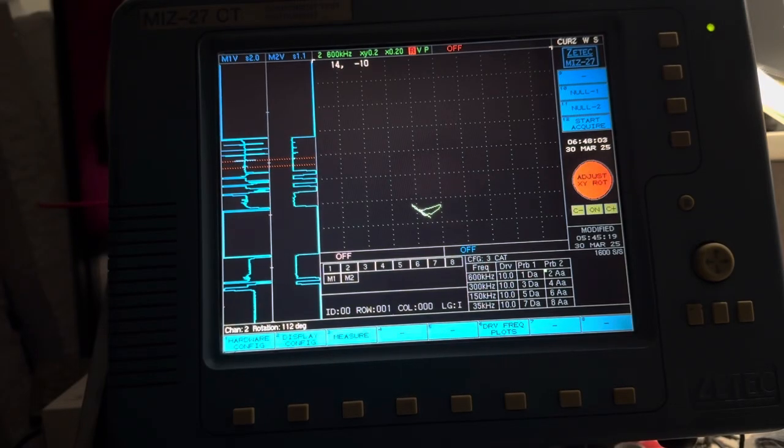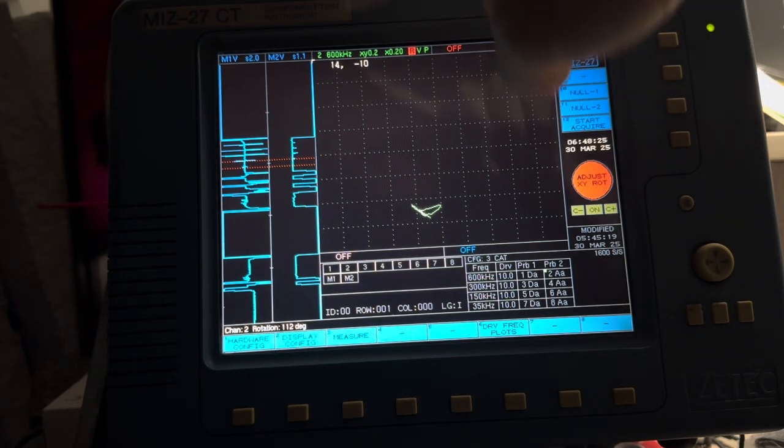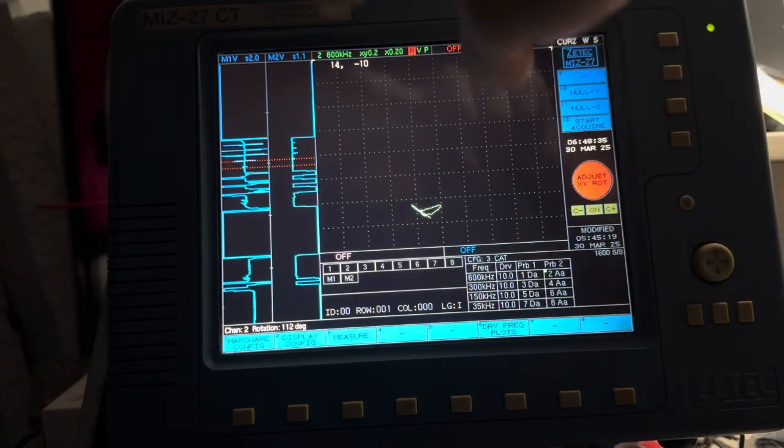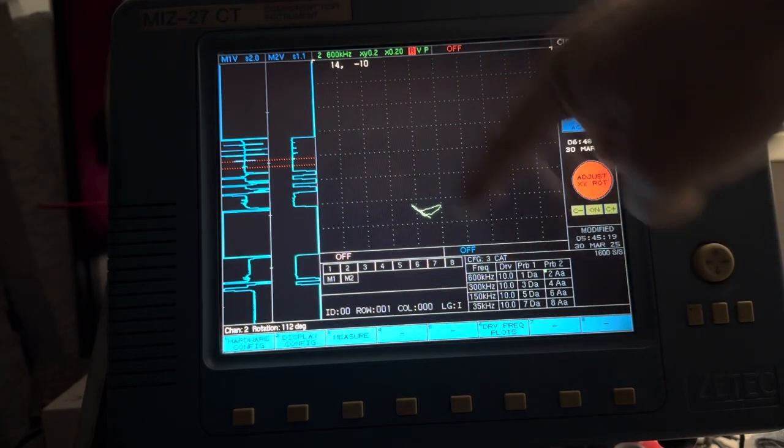In this video, we'll be talking about impedance changes and how data is actually evaluated in terms of impedance changes. If you recall from looking at impedance plane diagrams from your study books and your readings, you can probably remember that inductive reactance is usually shown on the vertical axis and resistance on the horizontal axis. And the liftoff line is always going down at this angle.